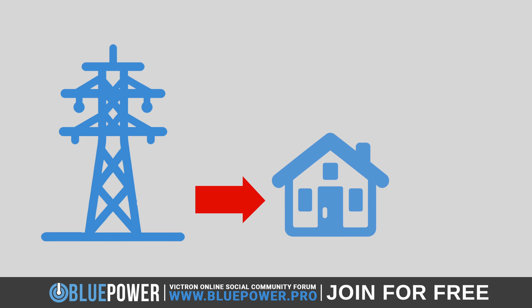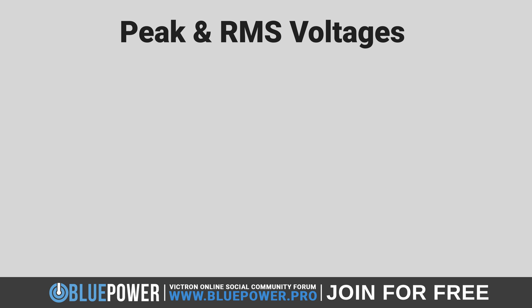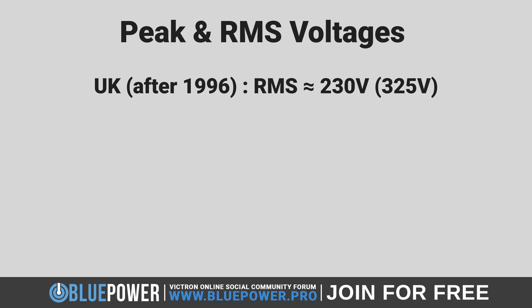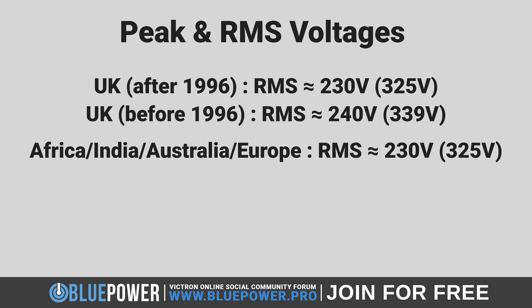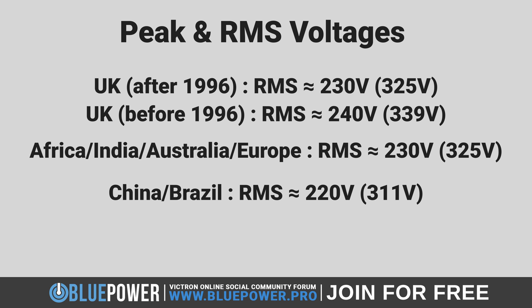When we talk about the electricity supplied to our homes or devices, we often refer to the RMS voltage — most familiar from plug sockets and multimeter readings. For the UK, after voltage harmonization in 1996, the RMS voltage is officially 230 volts, corresponding to a peak voltage of around 325 volts. However, due to historical standards and allowed tolerances, some locations in the UK may still experience voltages closer to 240 volts RMS, leading to a potential peak of about 339 volts. The same peak voltage of 325 volts applies to most other countries using 230 volts RMS, including Africa, India, Australia, and Europe. In China and some parts of Brazil, where the standard RMS voltage is 220 volts, the peak voltage would be approximately 311 volts.